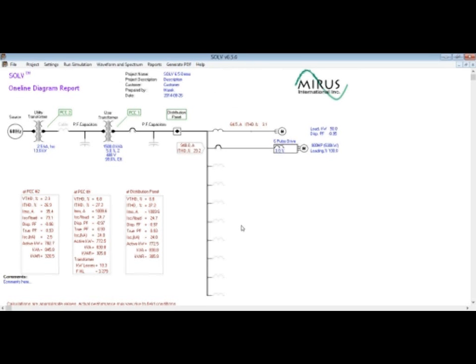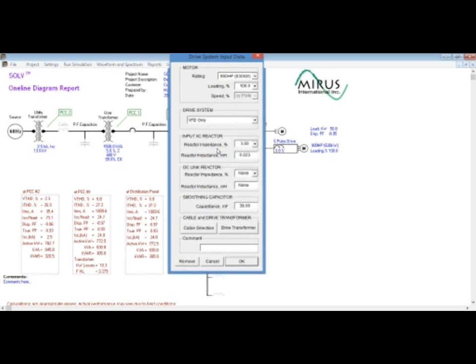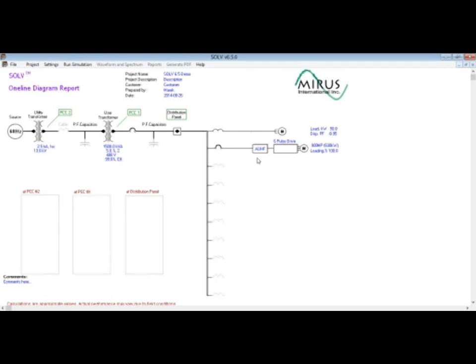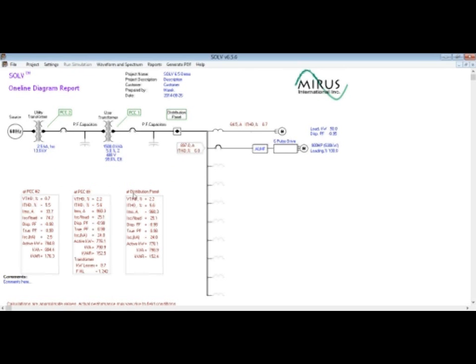So now that we have computed our simulation of the VFD without any harmonic treatment, let's add a Lineator AUHF filter to the VFD to see what performance we can get with it. So all we need is to click the breaker symbol on the load branch and open the drive system input data. And what we will do, we will change the drive system to the Lineator AUHF and click OK. You notice on the single line diagram the AUHF box appears, so now we can run the simulation with the filter.